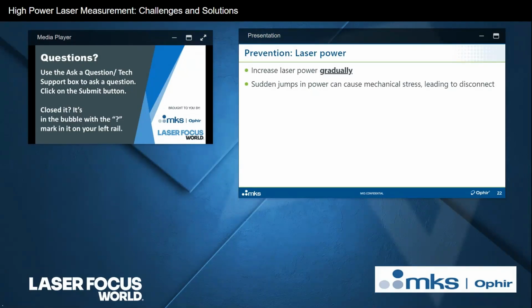So a highly recommended best practice that's related to this is not only make sure that the cooling water flow is on before you turn on your laser, but when you do turn on your laser, we recommend that you increase the laser power gradually. If the sensor is nice and healthy and everything is fine, then going from 0 to 30 kilowatts shouldn't be a problem if the sensor is designed for measuring 30 kilowatts. But if the sensor has even somewhat been exposed at some point in its past to a problem and that solder connection has been weakened, even if it hasn't been disconnected, then a sudden jump from 0 to a very high power might push it over the edge. So we recommend increasing the laser power gradually after you've turned on the cooling water flow, obviously. Those sudden jumps in power can cause mechanical stress, which could lead to disconnect, particularly if that solder connection has already been weakened, as I said, at some point in its past, but not necessarily so.